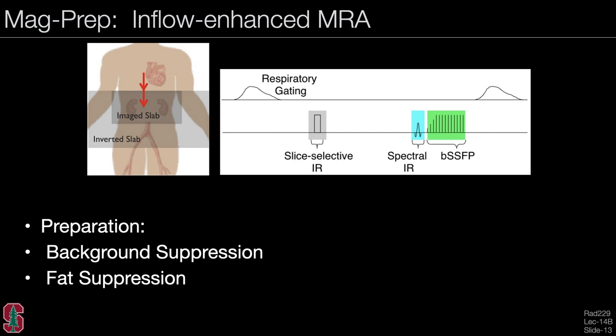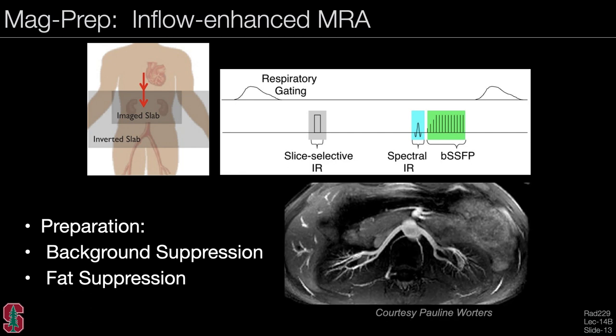Another example combines magnetization preparation approaches: inflow-enhanced magnetic resonance angiography. The preparation performs background suppression using a slice-selective inversion, waits some time, then does a spectral inversion recovery to suppress fat, then runs a balanced SSFP sequence. During this inversion time the blood flows into the slice, so ideally all static tissue is suppressed and we get a blood-selective image. The result shows renal arteries quite clearly without the use of a contrast agent—we simply take advantage of blood flowing into the slab quickly to create bright blood signal against a suppressed background.